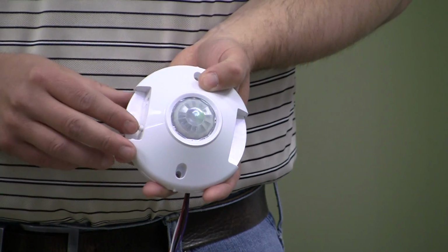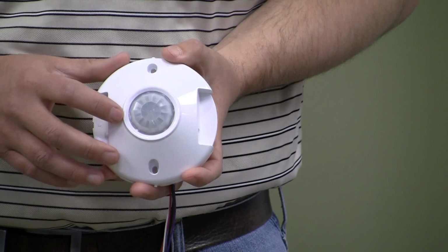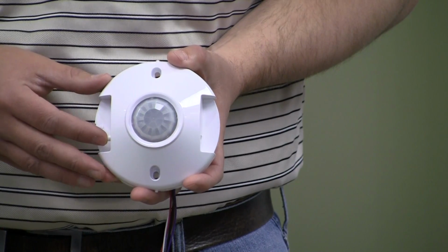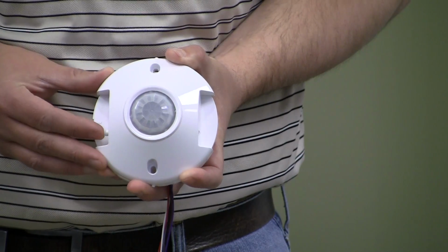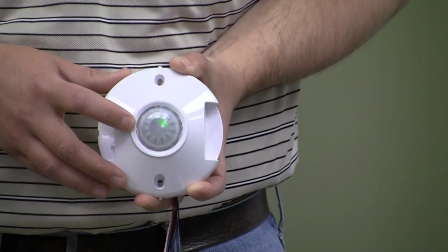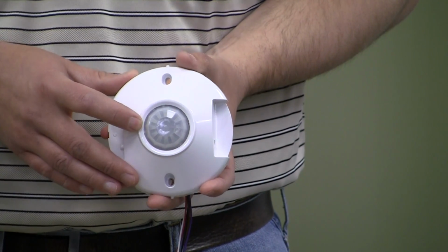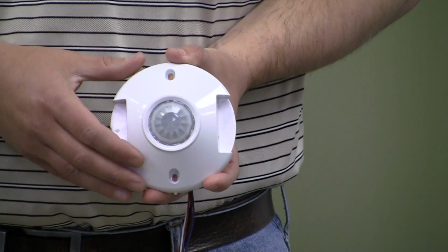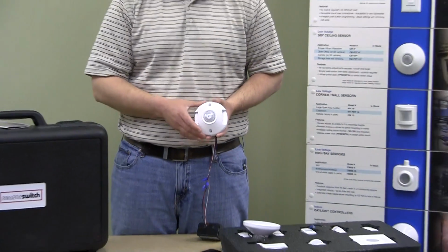So to do the occupancy time delay, we'll push that button twice. That gets us into the programming function for the time delay. This one is set for the default, so it'll blink back at us 5 times. If we want to make an adjustment, let's push it 9 times, which sets it to 20 minutes. Now the sensor is going to blink back at us 9 times. It'll do this blink back a total of 3 times to confirm that that's the setting we want to put that value to. Once that is done blinking back at us 3 times, the sensor will exit the programming mode, and there are no other additional adjustments that need to be done to the sensor.